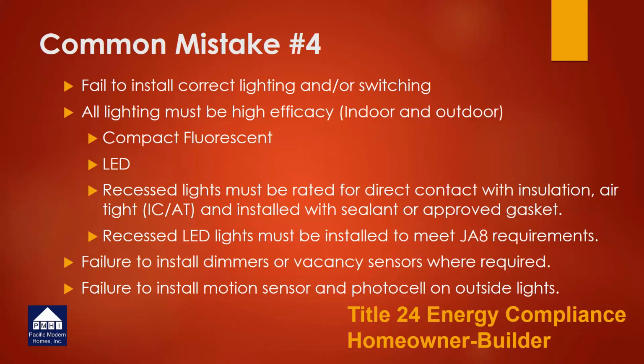But in order to be high efficacy, you're talking about installing compact fluorescent or LED, and if it's a recessed light fixture, it must be rated for direct contact with insulation, airtight, and installed with a sealant or approved gasket. And if it's a recessed LED light, it must be installed to meet JA8 requirements. This is an important issue. Building departments are catching this now. If you purchase your light fixtures from a local lighting store or electrical hardware location, they typically know what JA8 means. There's usually a label on the fixture itself or on the box that it's shipped in saying it is JA8, and it has to do with the efficiency of the light fixture.